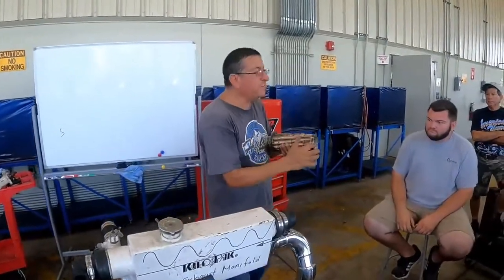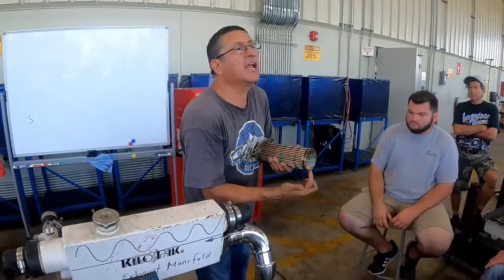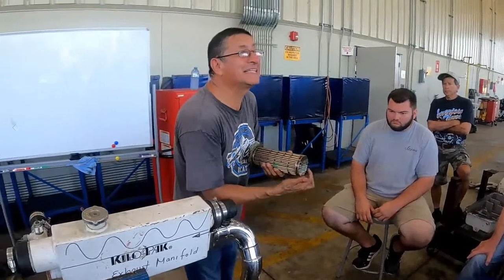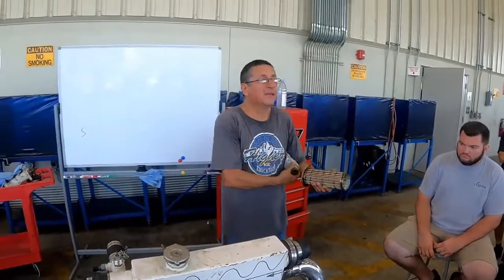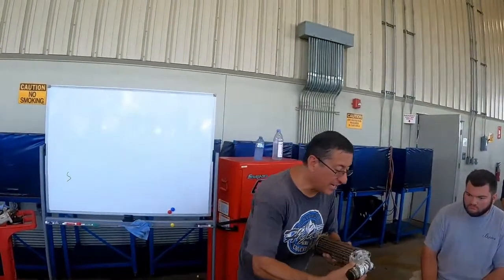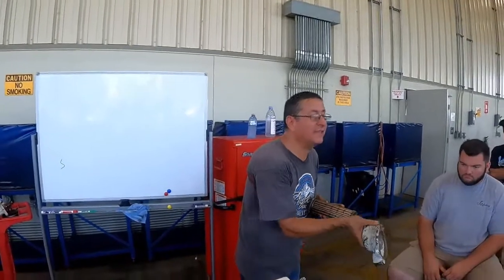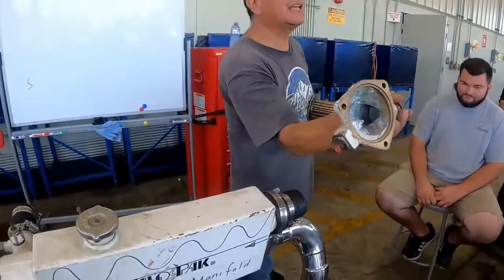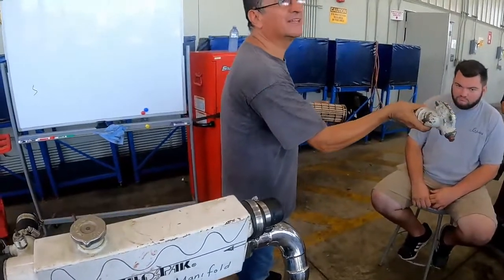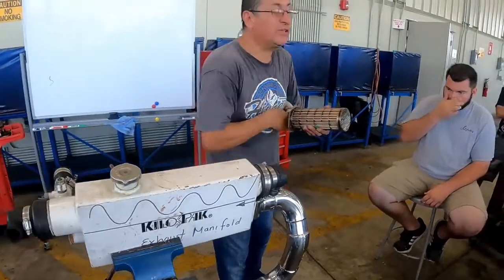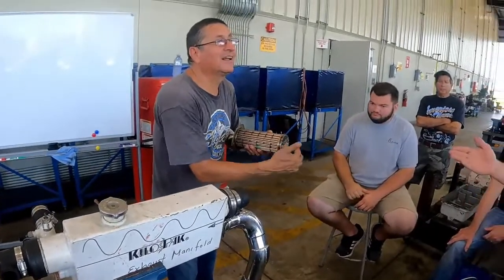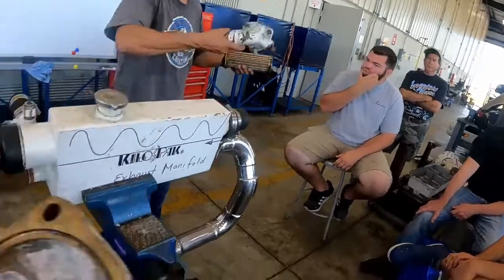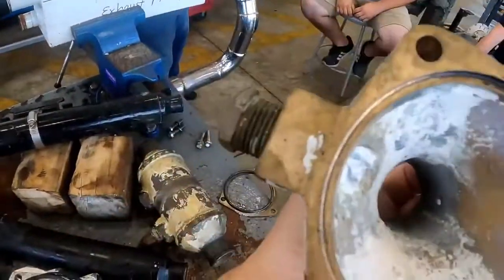Why are those pipes in the bottom clogged with calcium? And zinc. Why? Because of the radiator cap located here, look at the zinc. How is the condition of the zinc? It's destroyed, completely eroded. And what happened with those pieces of zinc? Now they're in there and clogged the pipe. For that reason, you need to replace those periodically.